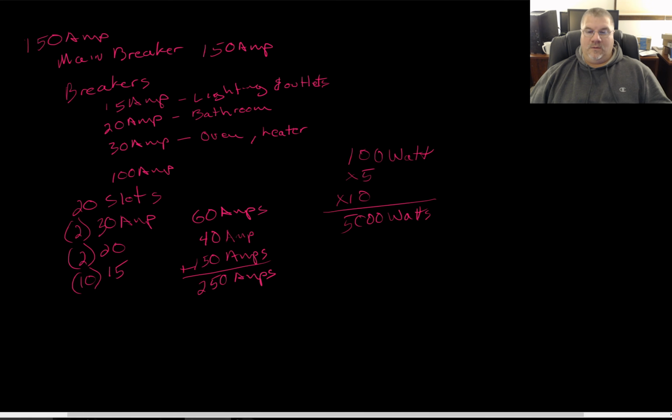Now, what does that watts convert to? There's P equals IV, right? That's power. So we're going to convert watts, 5,000 watts, divided by voltage, which is 120. That's what the V is, equals our current, which is going to be what? So let's say it's about 40 amps.